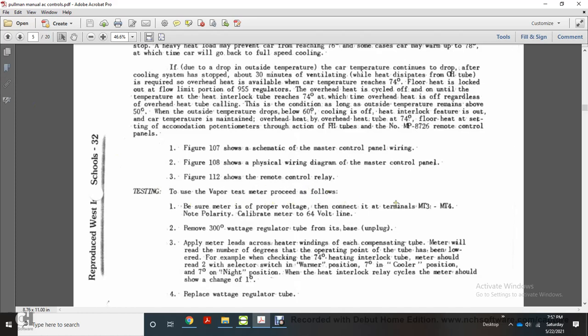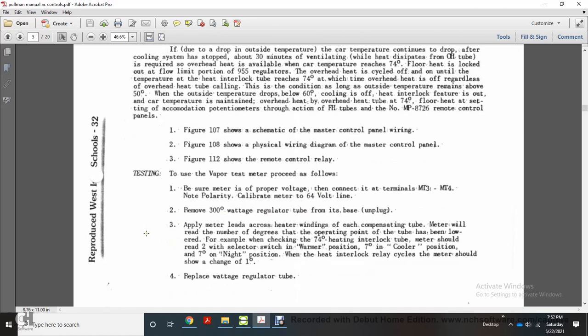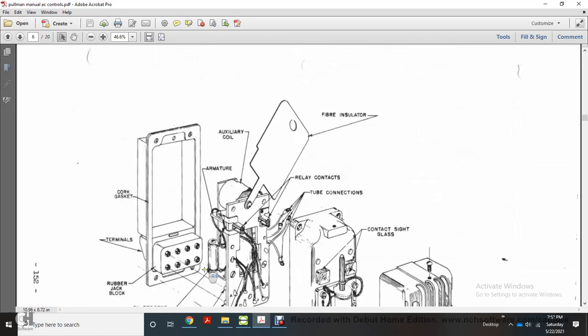Be sure the meter is properly connected to terminals MT3 and MT4 note polarity. Calibrate the meter with the 64-volt line. Remove the 300-degree wattage regulator tube from its base. Apply the meter leads across the heater windings of each compensating tube; the meter will read the number of degrees at the operating point. For example, checking the 74-degree heating interlocking tube: meter should read 2. Selector switch in warm position: 7 degrees. Cooler position: 7 degrees. Night position: when the heating interlock relay cycles, the meter should show a change of 1 degree. Then replace the wattage regulator tube.